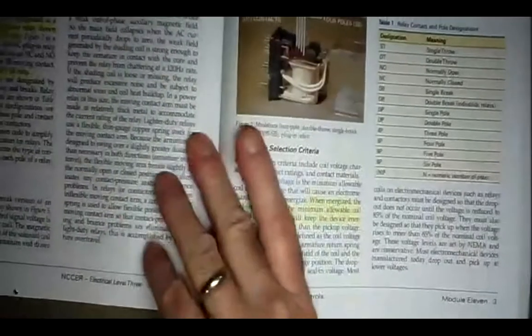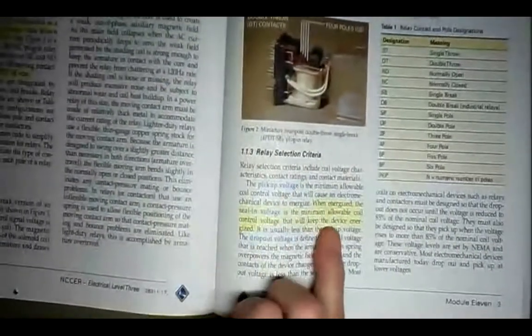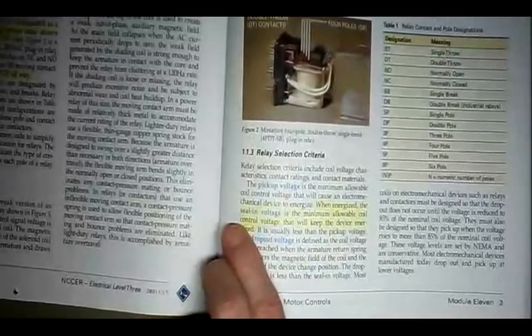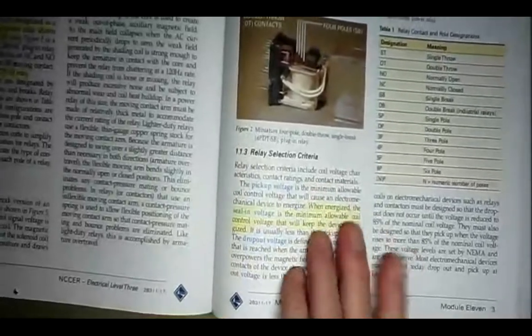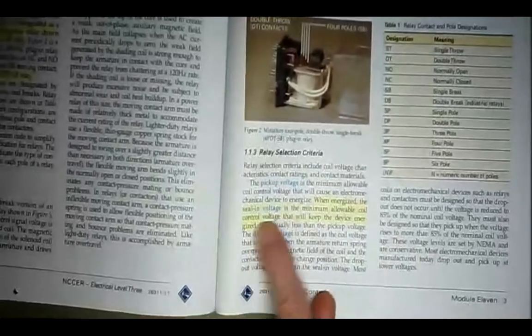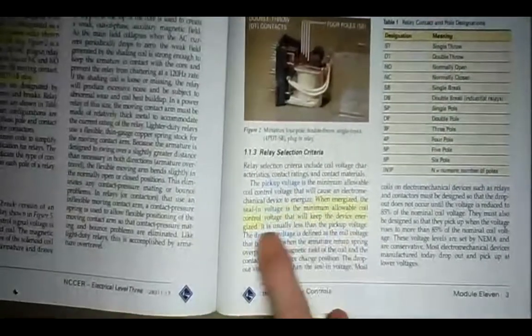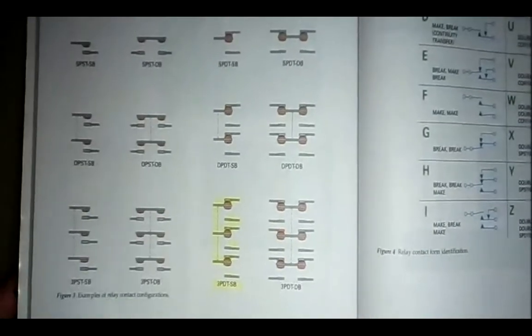What do they say? The pickup voltage is the amount of voltage needed to make it operate. The dropout voltage is the voltage at which it will let go. Seal-in voltage is the amount of voltage needed to keep it energized once it has closed, once the contacts are closed.